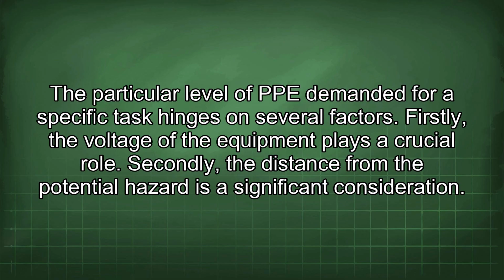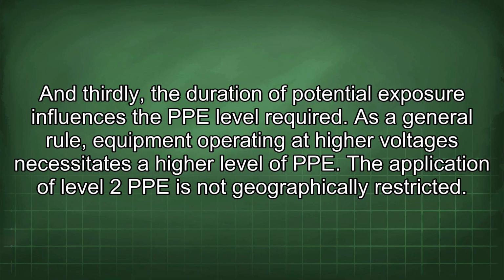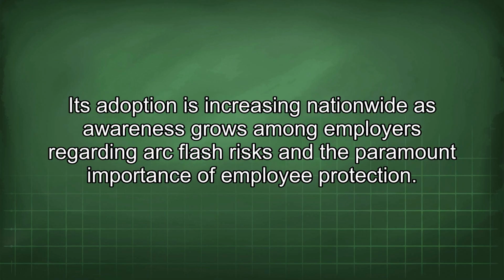Firstly, the voltage of the equipment plays a crucial role. Secondly, the distance from the potential hazard is a significant consideration. And thirdly, the duration of potential exposure influences the PPE level required. As a general rule, equipment operating at higher voltages necessitates a higher level of PPE. The application of Level 2 PPE is not geographically restricted. Its adoption is increasing nationwide as awareness grows among employers regarding arc flash risks and the paramount importance of employee protection.